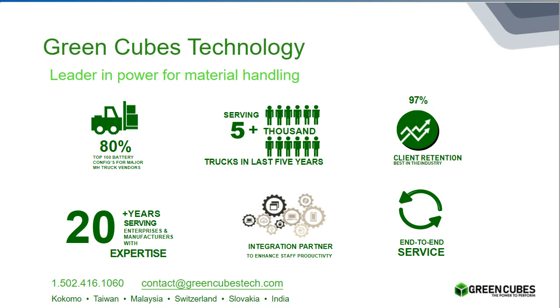Yeah, I briefly mentioned that just because cold storage is actually an early adopter of lithium-ion technology. That's because lead-acid batteries can't be used or charged at very low temperatures, especially charged, whereas lithium-ion batteries, ours actually incorporate heaters that keep the batteries at an optimum temperature. So they can actually be used and charged in a cold storage or refrigerated facility, which means that you don't have to stabilize the temperature of the equipment going in and out of the freezer, and that helps keep down frost and things like that. That can actually cause dangers for people.